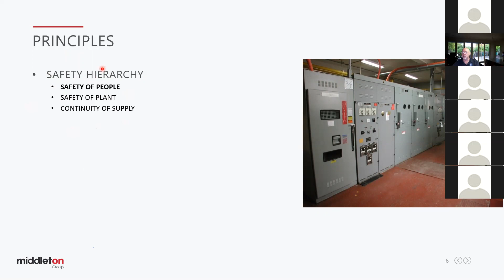So when it comes to setting up access systems, safety of people comes first. The next principle for safe operating is that there's a visible break between the source of high voltage—or any voltage for that matter—and the part of the system or plant that's worked on, and there's a lockout or tag out mechanism, which means a deliberate act has to be taken to re-energise the system. It can't happen inadvertently.